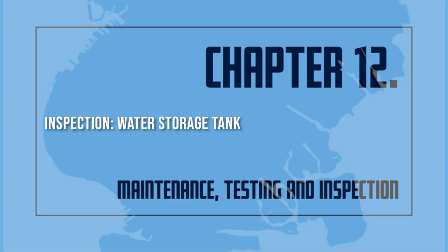The temperature of water in the tanks with low temperature alarms connected to a constantly attended location shall be inspected and recorded weekly during the heating season. Air pressure. Air pressure without a supervised air pressure source shall be inspected monthly. Air pressure with a supervised air pressure source shall be inspected quarterly. Heating system. The heating system and components, including piping without a low temperature alarm, shall be inspected daily. The heating system and components, including piping with a low temperature alarm, shall be inspected weekly.